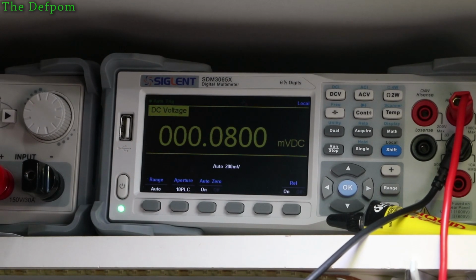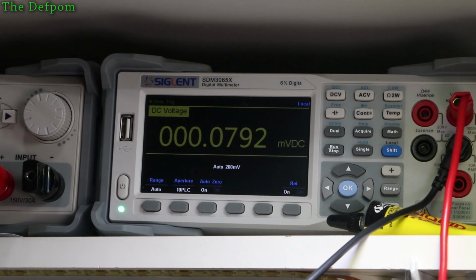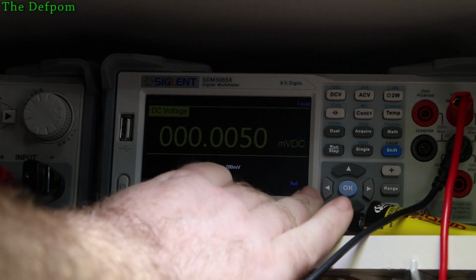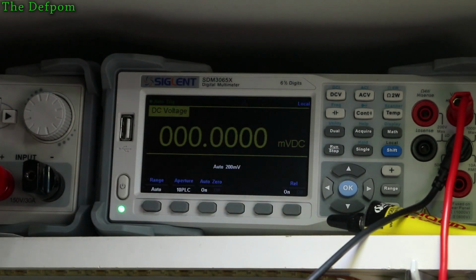So what I'll do before I actually do that calibration is I'll link these leads together in place, because it's such a fine value, and make sure I've got it zeroed properly, because it's supposed to be within 2 microvolts, and as you can see I'm sitting at 6 here. So let's offset that there like that. There we go. Hopefully moving the lead by a couple of inches doesn't matter.